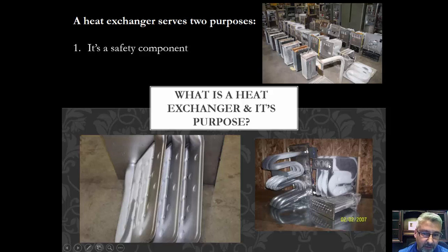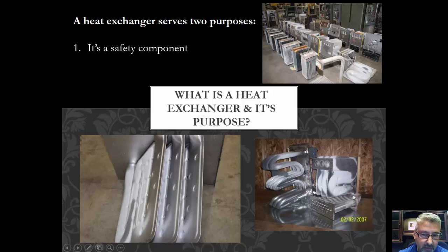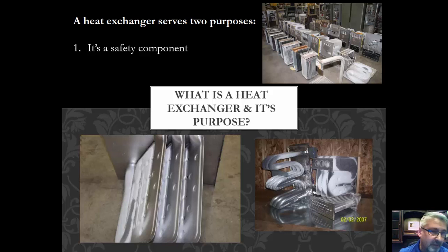The burners on this furnace would be right here — you'd have three in-shot burners. The heat and flue gas from those burners will travel through the serpentine heat exchanger, work its way into the coupler box, then go through the secondary. On the front would have been a collector box or front cover with a vent motor assembly. That flue gas produced from the fire must exit the building via chimney, B vent pipe, PVC schedule 40, or cell core, depending on what the furnace is rated for.